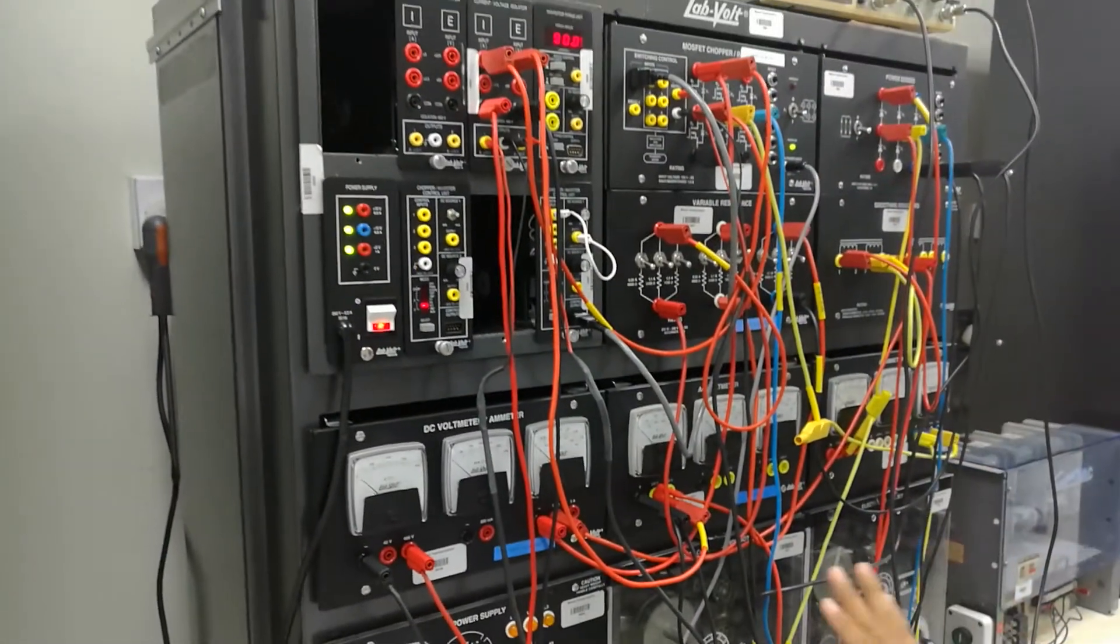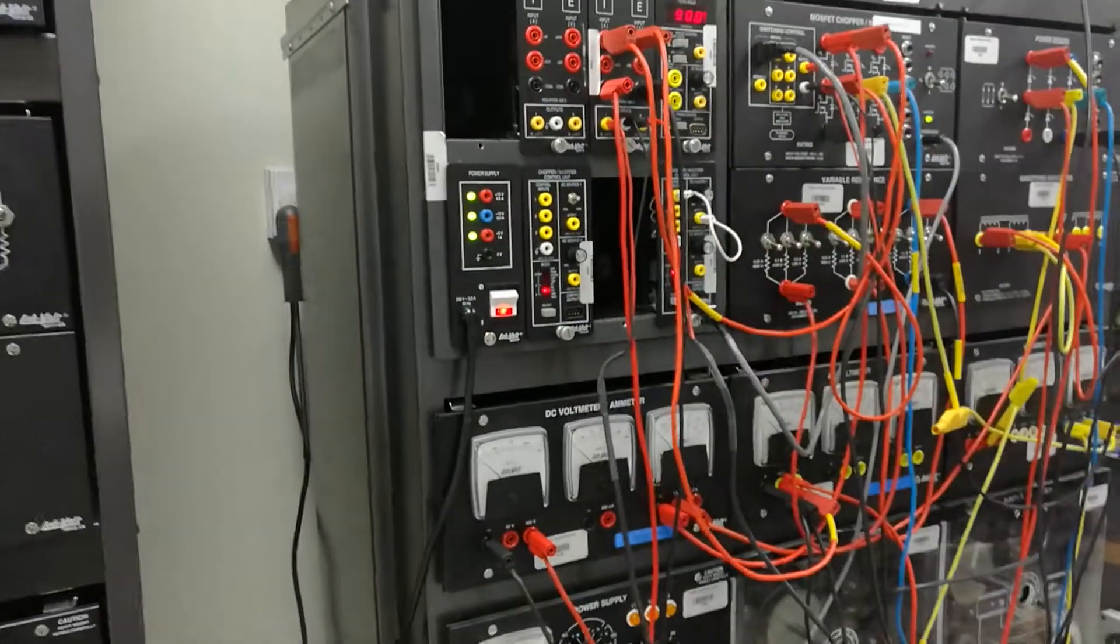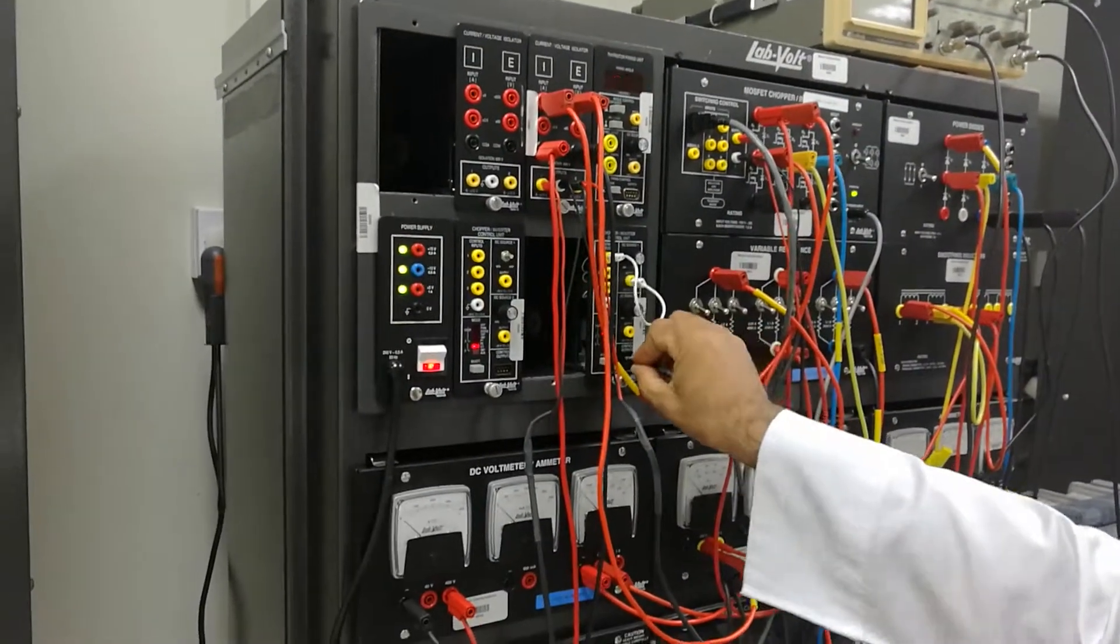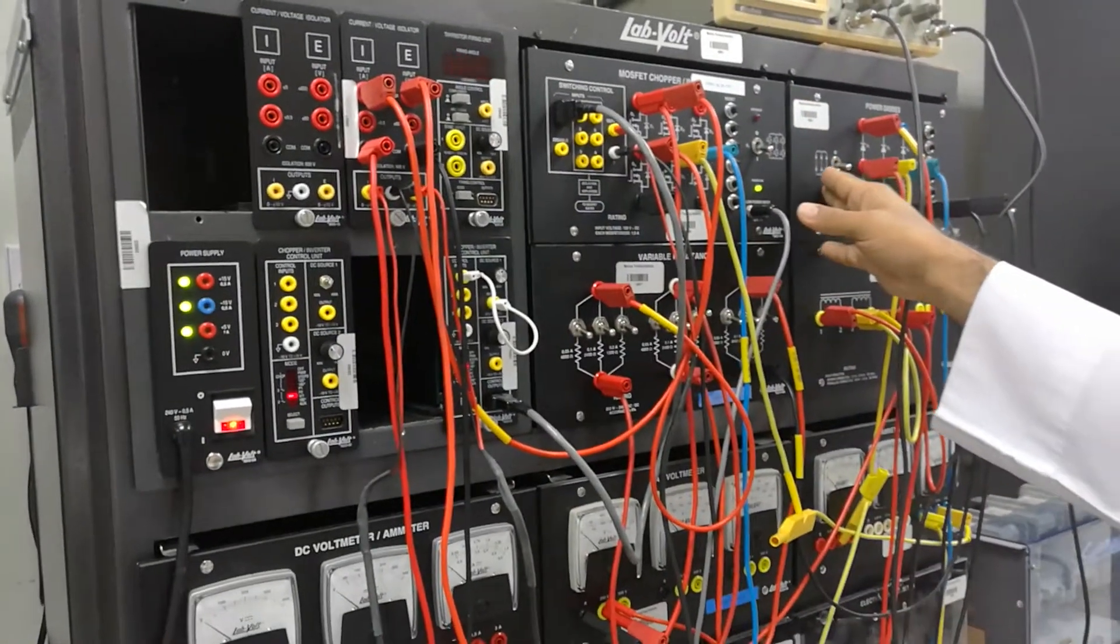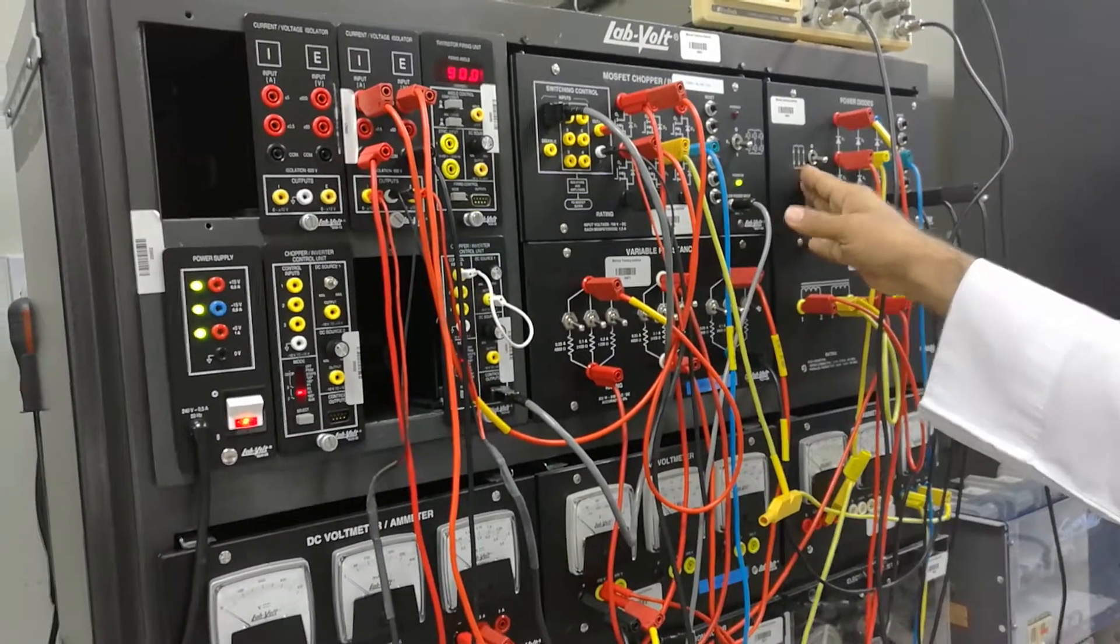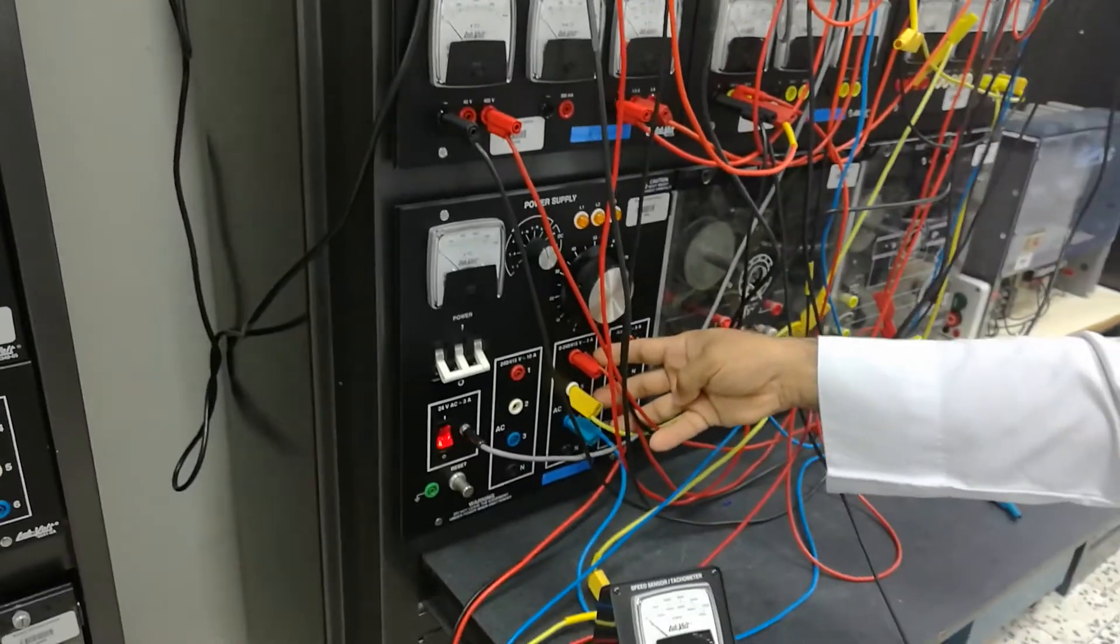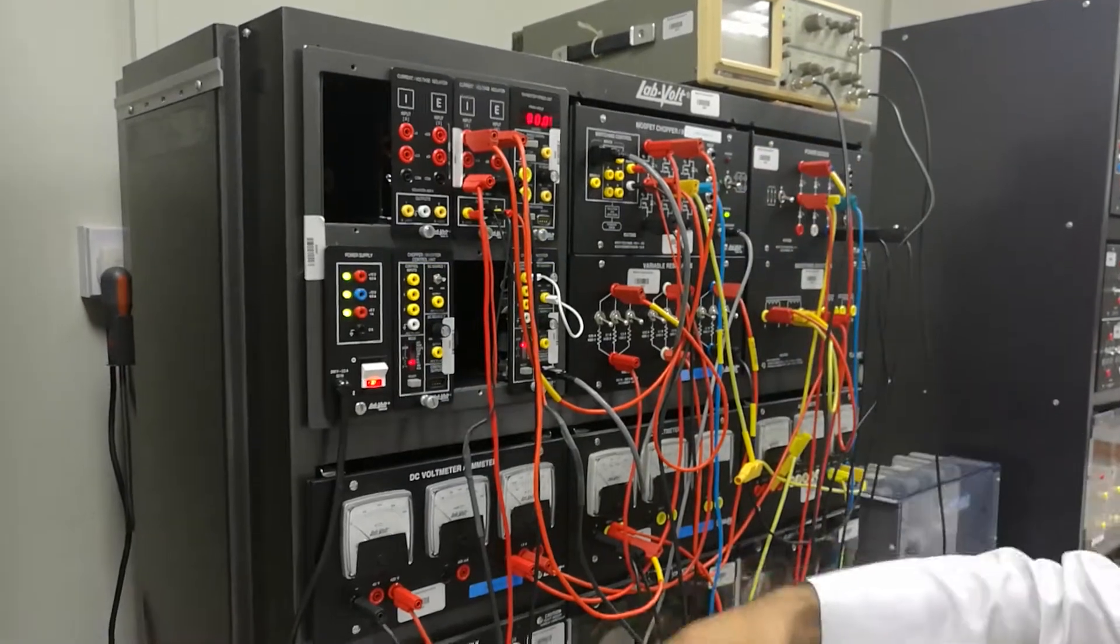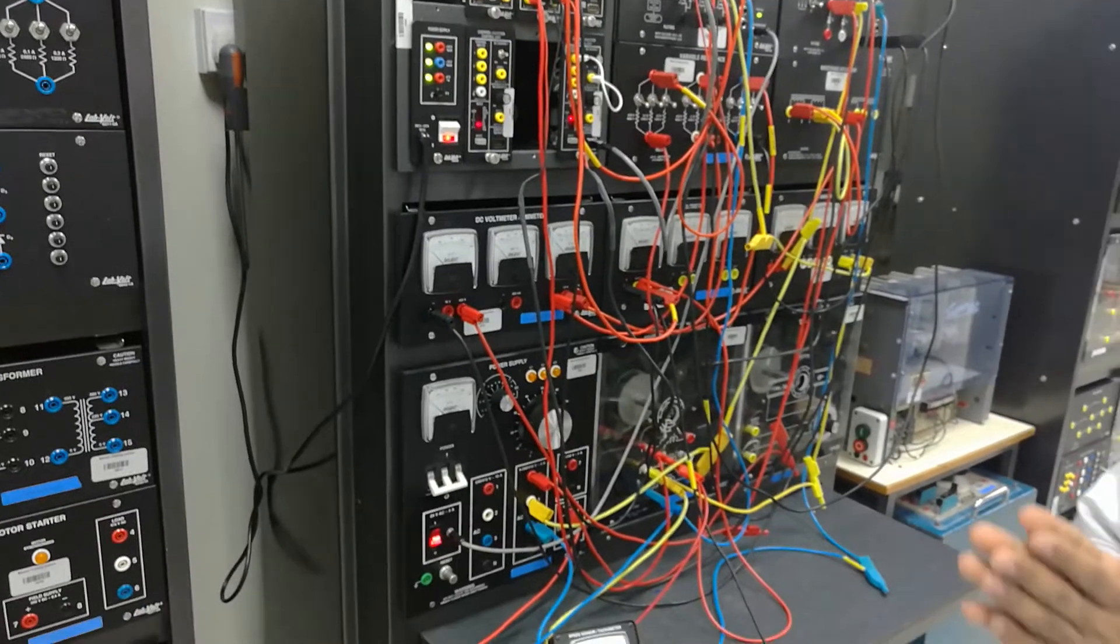We have a frequency converter using the 180 degrees method. This is the controller, this is the MOSFET inverter, we have a diode rectifier. The idea is to convert the power supply three-phase AC into DC, then from DC to variable frequency AC. So this is a variable frequency drive.